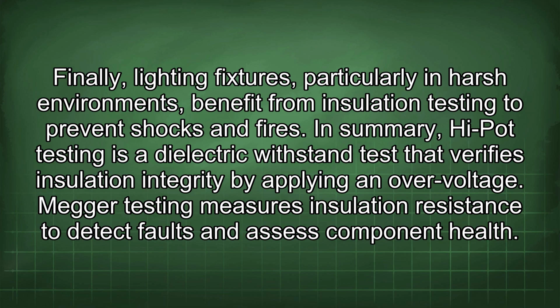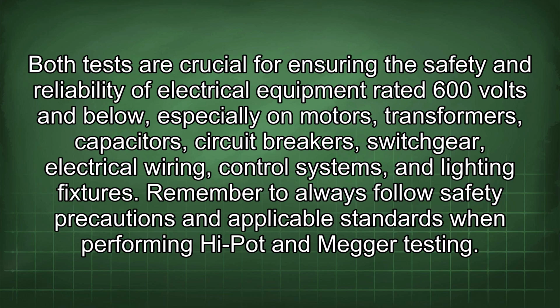In summary, Hi-Pot testing is a dielectric withstand test that verifies insulation integrity by applying an overvoltage. Megger testing measures insulation resistance to detect faults and assess component health. Both tests are crucial for ensuring the safety and reliability of electrical equipment rated 600 volts and below, especially on motors, transformers, capacitors, circuit breakers, switchgear, electrical wiring, control systems, and lighting fixtures. Remember to always follow safety precautions and applicable standards when performing Hi-Pot and Megger testing.